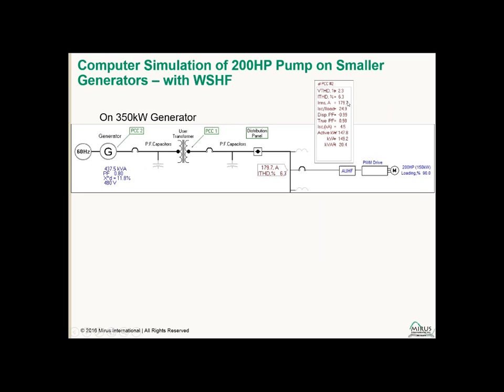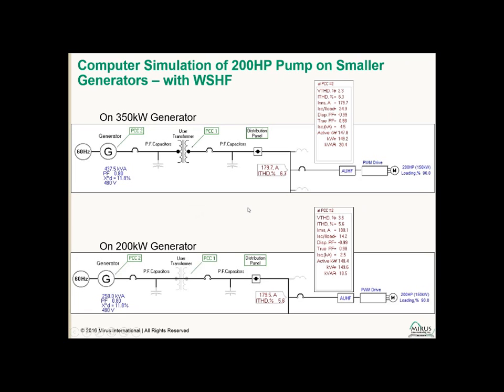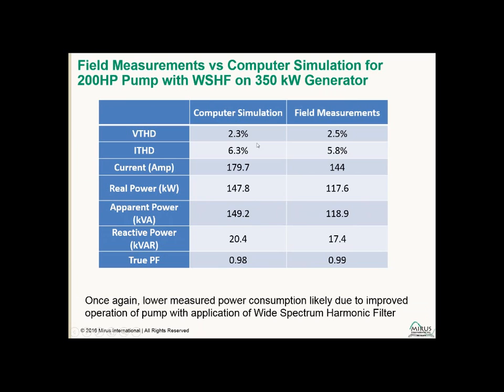If we look at that, we can see that there's still very low current distortion and voltage distortion, so that would meet all of the harmonic requirements. They could have gone to a 200 kilowatt generator and still would have had low current and voltage distortion. But like I said, our customer was too nervous about the fact that they had so many problems before and decided to choose a 350 kilowatt generator instead.